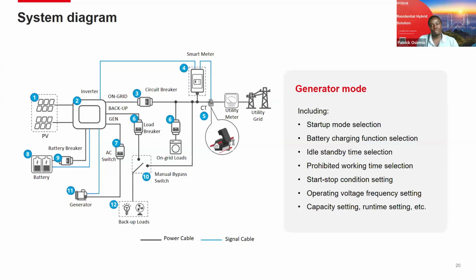Now, how the connection looks. It's quite easy. We have two options. The inverter itself comes with the CT. If the position where you're mounting your CT and the position where you're mounting your inverter are less than 25 meters apart, then you can use the CT. Similarly, if they are more than 25 meters apart, then you'll have to purchase a smart meter. The CT will connect to the smart meter, and then the smart meter will push information using the Modbus protocol to the inverter for longer ranges. So up to 100 meters can be achieved when you're using a smart meter.